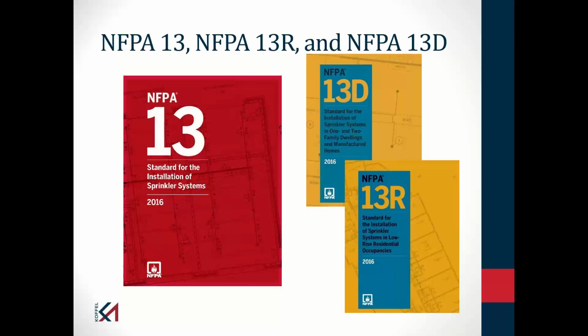And it really wasn't designed for that. It was set up for single family dwellings. So NFPA came out with a third standard around 1985 for low-rise residential occupancy. This is generally limited to a 4-story building, ties into fire department access, because again, 13R does not require things like a concealed combustible attic space to be provided with sprinkler protection.